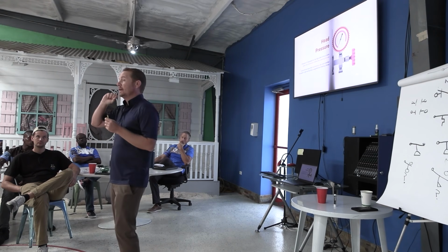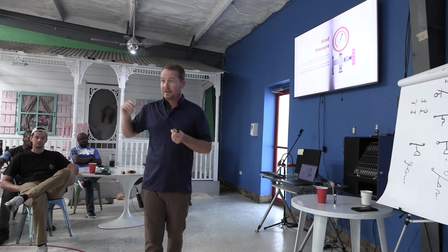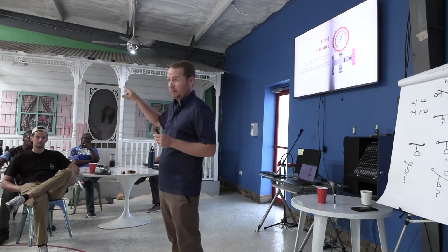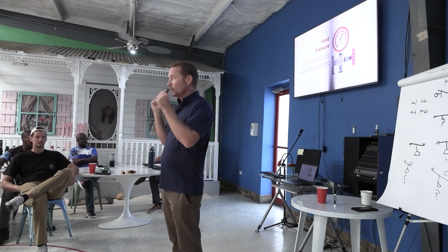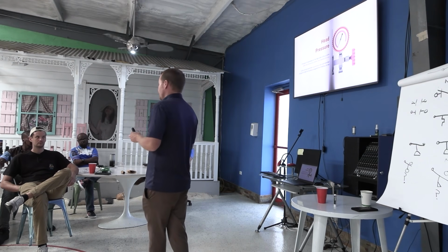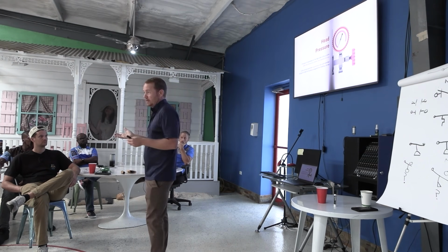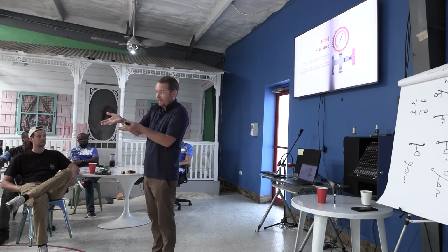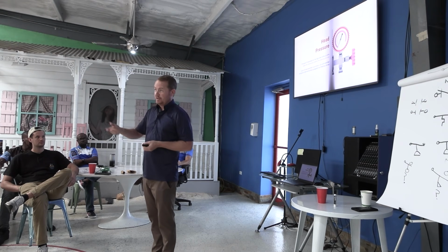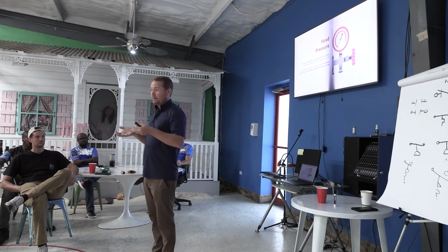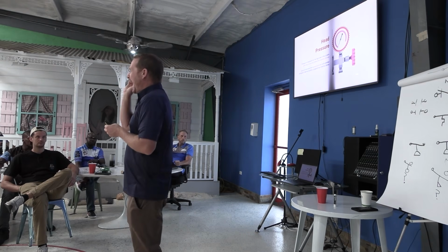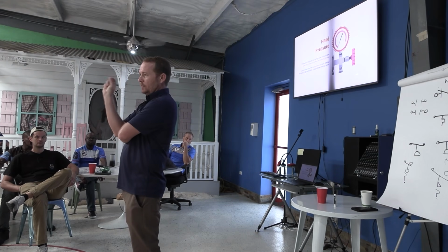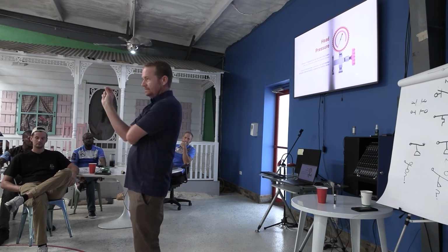Now, if I was talking about in a refrigeration context, when I said head pressure, that's exactly what I'd be talking about. Because if I meant liquid pressure, I would have said liquid pressure, right? So this is where words become really important. If you find yourself ever working on a package unit, for example, the only port is generally on the discharge line. So you got to know that those are two different things. We're talking liquid pressure. But what are we actually talking about when we're talking about liquid pressure? What do we really care about?